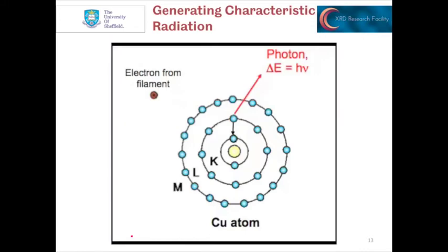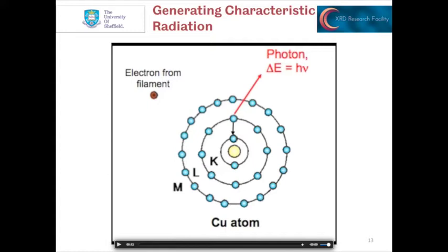We can view this in this short animation, where we have an electron from the filament impacting with an atom in the metal target, causing a core electron to be ejected. This leaves an unstable configuration with a hole present in one of the core shells. An electron then transfers down — in this case from the L shell to the K shell — to fill this core hole and stabilize the atom. In doing so, it releases a photon where delta E equals h times the frequency. For many metal atoms, this energy is in the range of X-radiation.